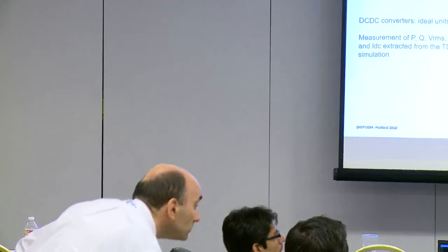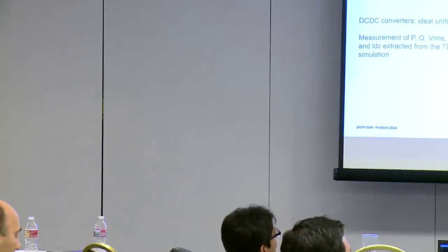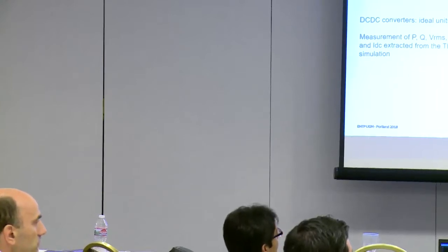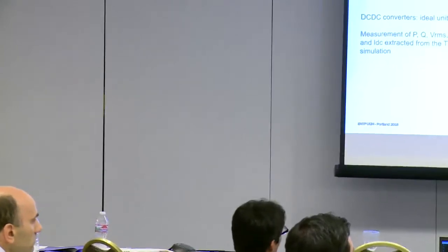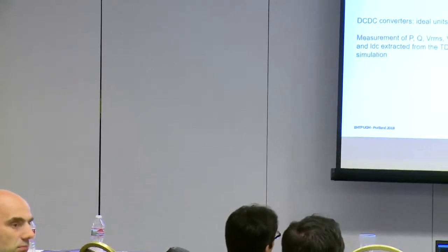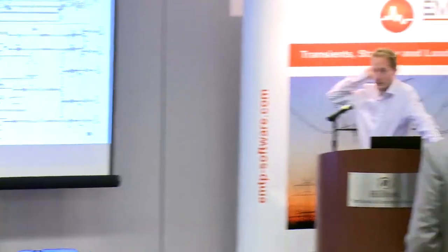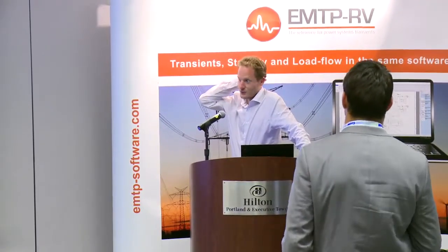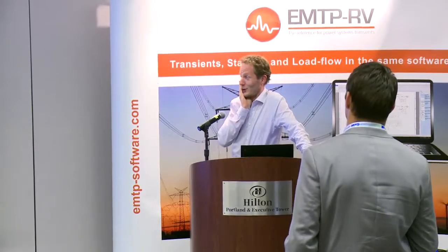And did you ever have matching results with other software? For this test, it has only been developed in EMTP. What about the smaller one, like BM4? The BM4, which is the first test system, we did many tests with PSCAD, and the two software give the same results, even in transients. We spent something like 1 week with the guy from PSCAD just to compare.